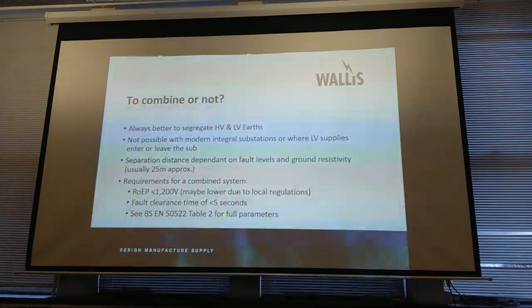50522 does talk about a stress voltage of 1200 volts. So you're not actually forcing more than 1200 volts up the LV of an office block or something like that. They're saying that laptops, lights, projectors, etc. should have a withstand of somewhere between 1000 volts and 1500 volts. And so by the time you've got a bit of impedance on that, coming up the network, 1200 volts rise of earth potential should be all right. And by bonding the two together at that, you should be okay.